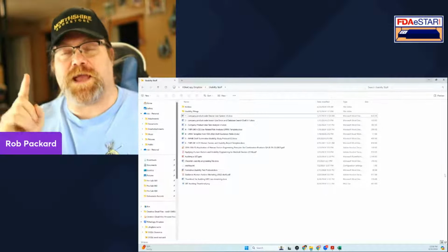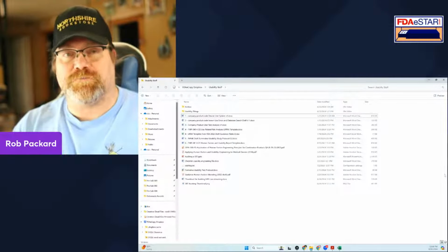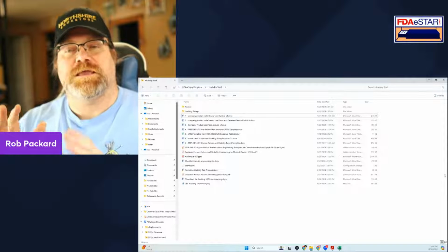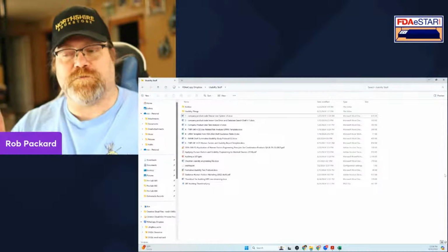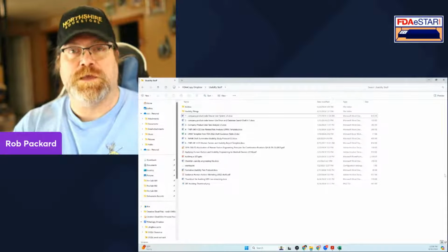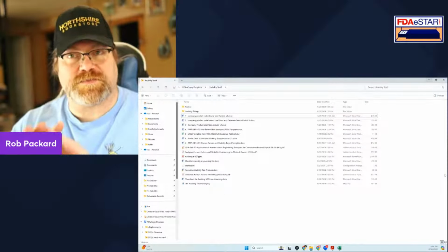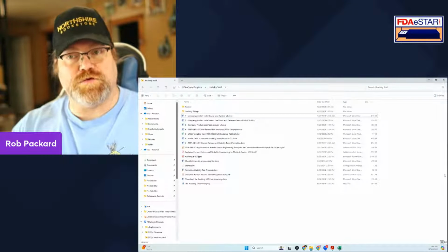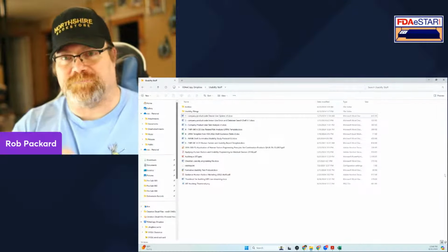file. And there actually is a standard that you should be following. It's IEC 62366. And that should be the standard that you're following for building your usability engineering file. So if you're doing anything in Europe, you're going to have to provide that as part of state of the art for your technical file. And the usability engineering file is just a piece of that.